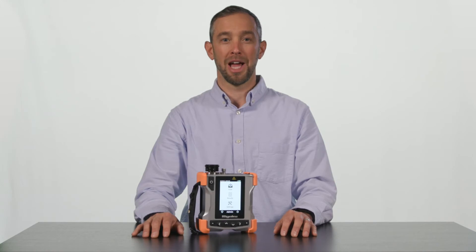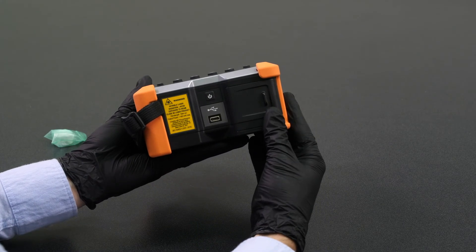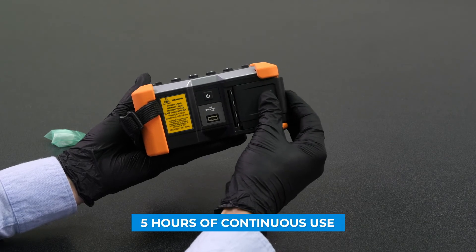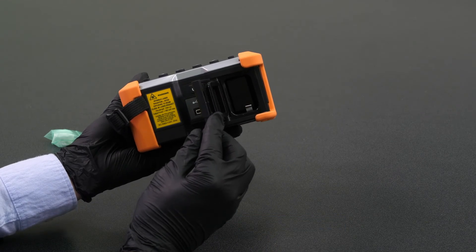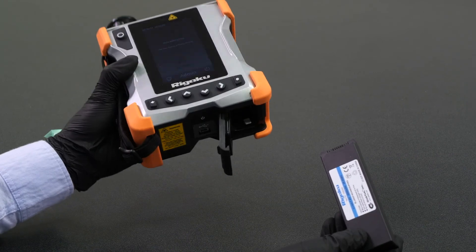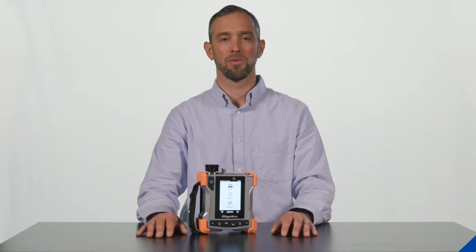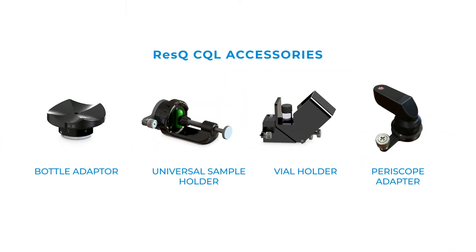The removable, rechargeable, and hot-swappable battery sits behind a sealed waterproof door at the bottom of the instrument and offers 5 hours of continuous use. The ResQ CQL is also compatible with disposable 123A batteries. There are a number of adapters and accessories available to make sampling even easier for a diverse range of applications and sampling environments.